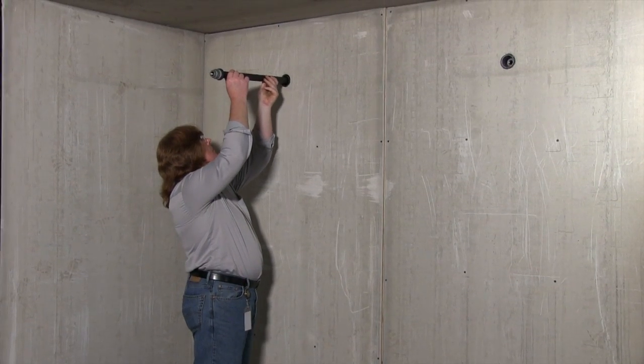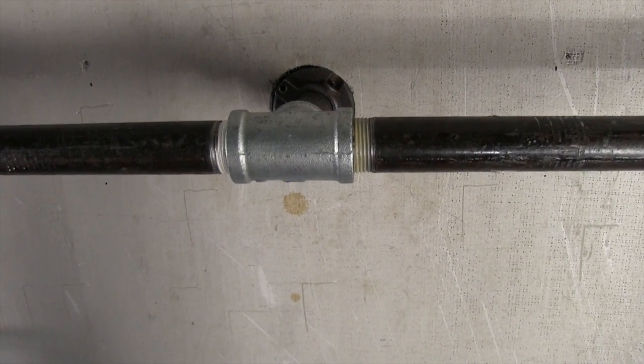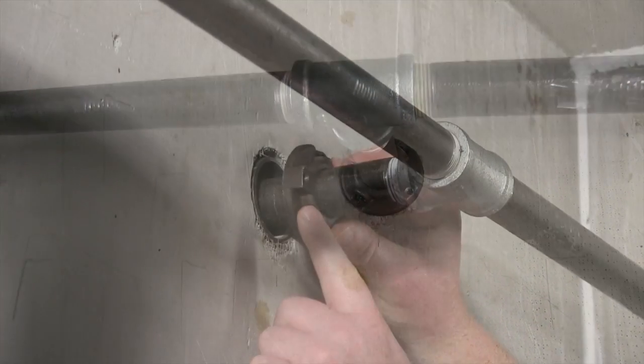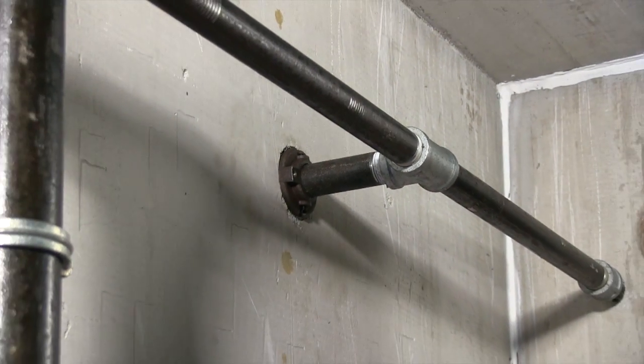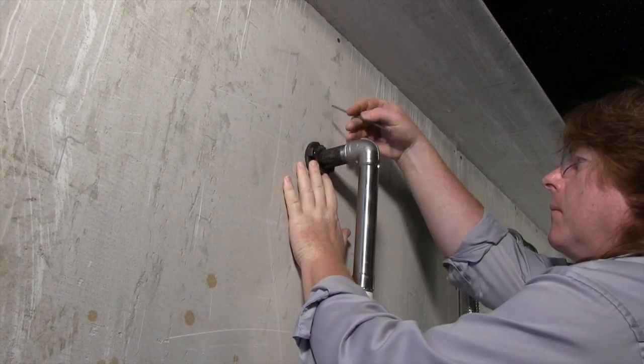When the threaded end of the sprinkler pipe first protrudes from the sleeve on the rear of the installation, slide on the retaining flange but do not yet tighten the pipe set screws. Make the threaded end of the sprinkler pipe into the supply pipe fitting. When utilizing a rigid pipe installation, ensure the sprinkler pipe and supply pipe share a common center line. This will ensure the sprinkler pipe is centered within the pipe sleeve and enables a square sprinkler and escutcheon installation. Once the sprinkler pipe is made into the supply pipe fitting, slide the retaining flange against the rear wall, ensuring the neck of the retaining flange is inserted into the inner diameter of the 2-inch Schedule 40 steel pipe sleeve. Utilizing a flexible pipe connection makes centering the sprinkler pipe and ensuring a square and flush installation much easier, as the sprinkler pipe and supply pipe do not need to share a common center line. For this reason, a flexible connection is recommended for all Raven Sprinkler installations.